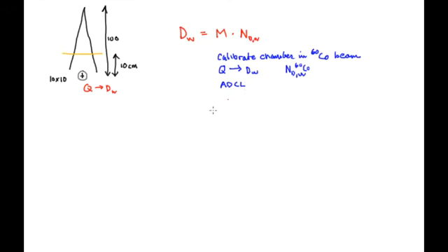All right, so let's look at how this might actually work. You would get your meter reading M, multiply by this N_D,w calibration factor, and that should give you the dose in water, right? Actually, no, that is not right. It's close, but this is the N_D,w in a cobalt 60 calibration beam, but your beam is not a cobalt beam up here, it's a LINAC. Let's say it's a 6 MV beam or something. So you can't just simply multiply by the calibration factor.